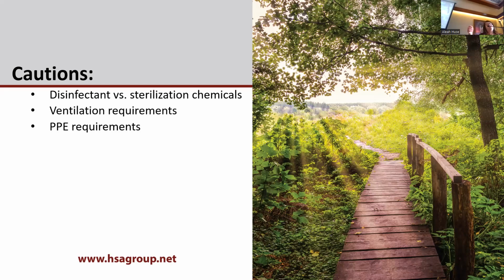It's more so a caution if you're doing the cold sterilization. That's again, do not do that. But if you're soaking in your clinic, make sure that you are aware of the expectation for ventilation for your staff and you're able to show you're meeting that requirement. And then PPE. I do find the majority of the time we find gloves and all of the PPE supplies needed. But especially if you're doing cryotherapy, that switch of nitrogen from the big tank into the little unit you're taking in for patient use, make sure you have those insulated gloves and goggles and all of those things that you need to ensure your staff are safe as well. That's not necessarily instrument related. It just popped up because, oh boy, we see that often missing.